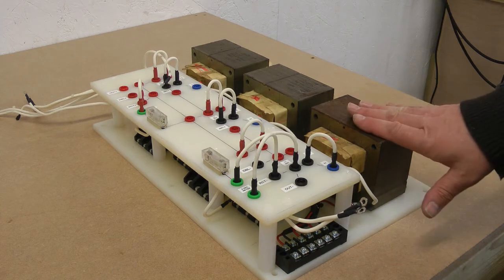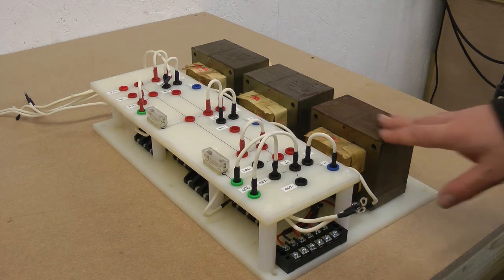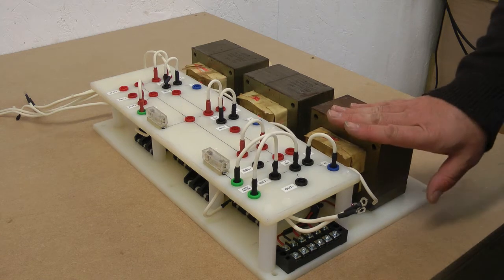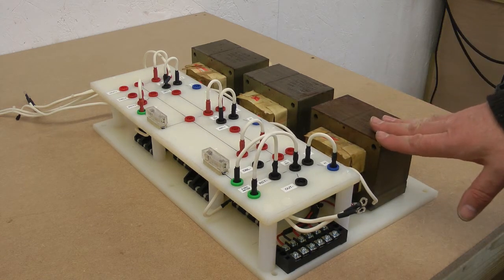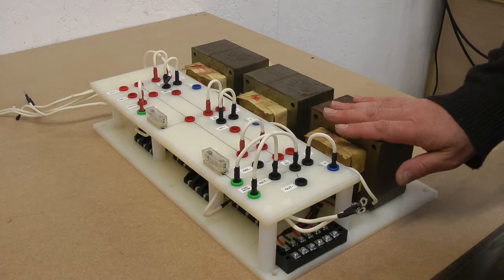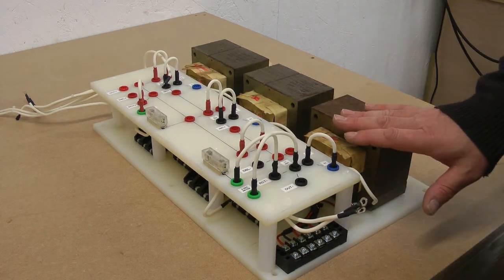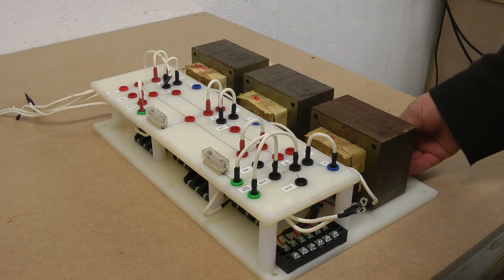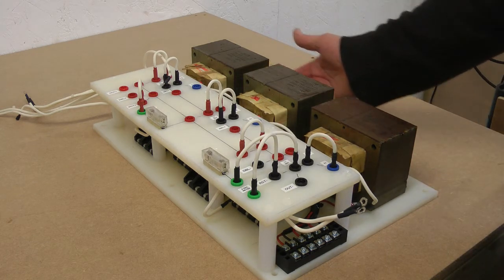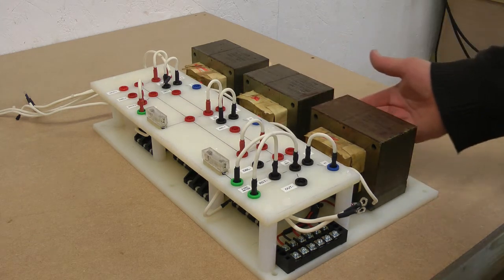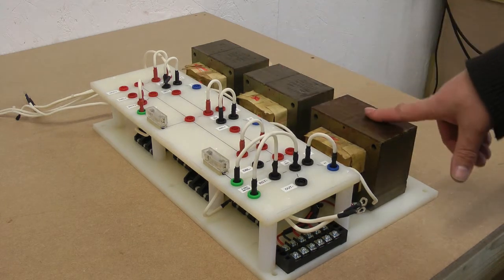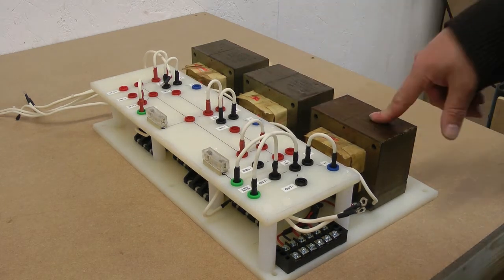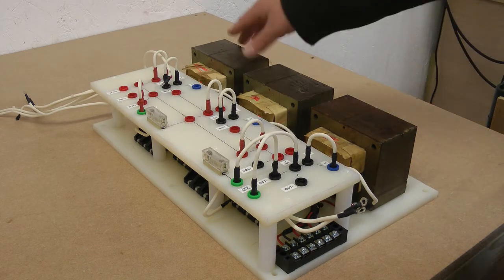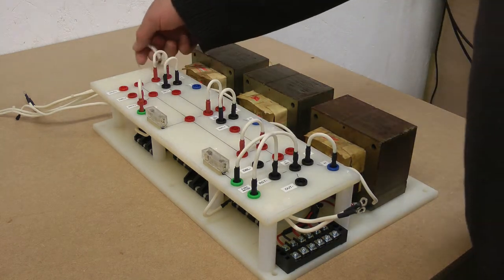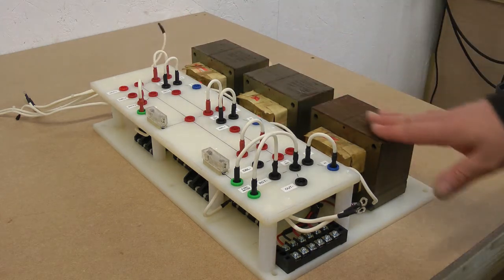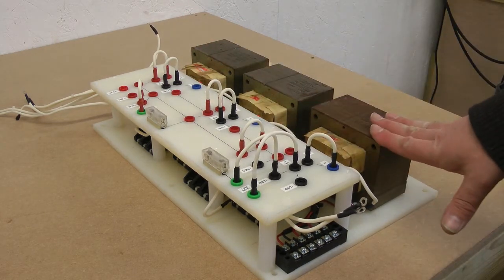The phasing of these can also be switched. From the front panel, as I've already shown, the switches can be adjusted to be off, so all transformers can be off or all on, and the phase of the live and the neutral to the primary can be switched. For example, if they're running in series in the way that I said before, with 2 up, 1 down, you have 2 in phase, 1 anti-phase. If you're running all 3 in parallel, then you run them all in the same phase.